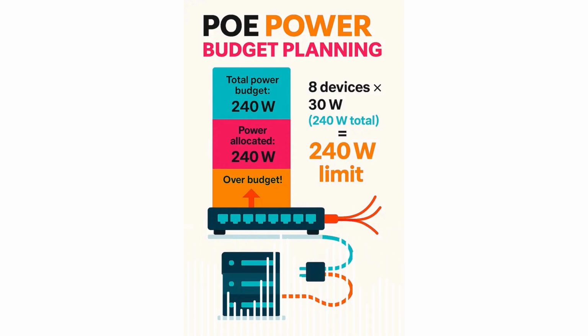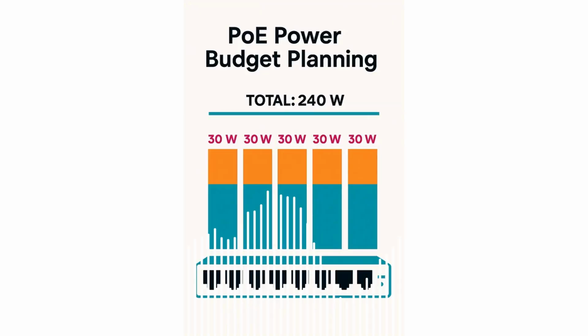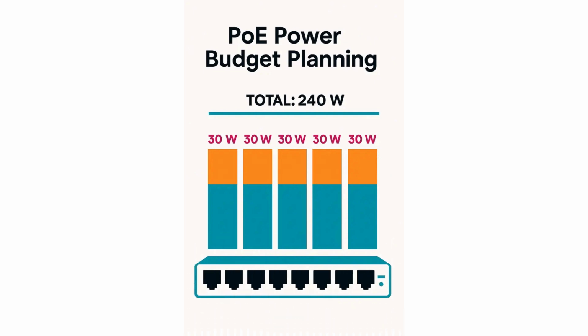So you can't start fires. You can use low voltage technicians to install it. You're using about 75% less copper. Electrical and copper costs are just skyrocketing right now. So the fact that you can use thinner wires, it's safe to touch, and you can distribute it throughout your building without conduits is a huge bonus today in construction.